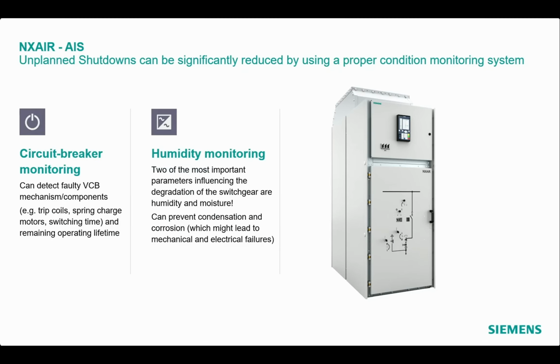Circuit breaker monitoring can help to detect faulty vacuum circuit breaker components like trip coils, spring charge motors, but also can give a remaining operating lifetime prediction. Humidity monitoring is essential in an AIS, as humidity and moisture are the two most important parameters influencing the degradation of the switchgear. It can also prevent condensation and corrosion, which might lead to mechanical and electrical failures.